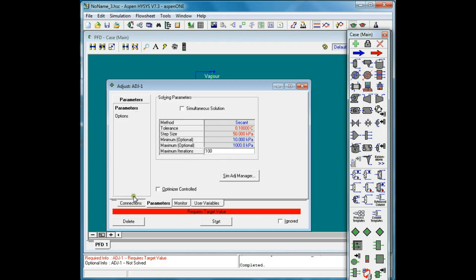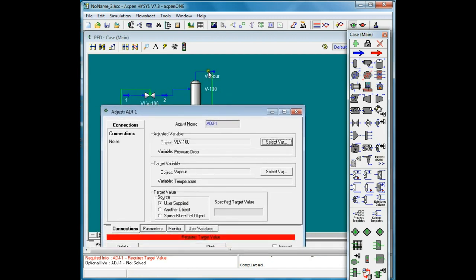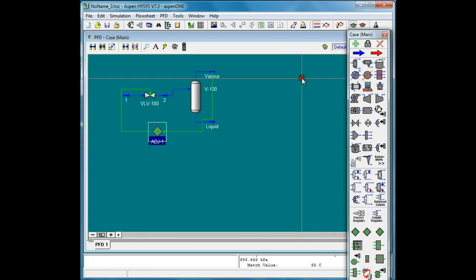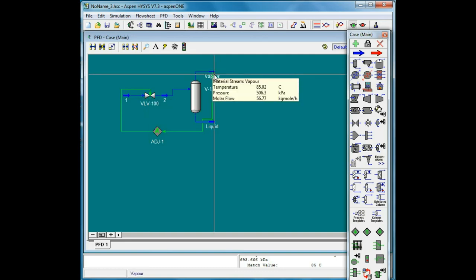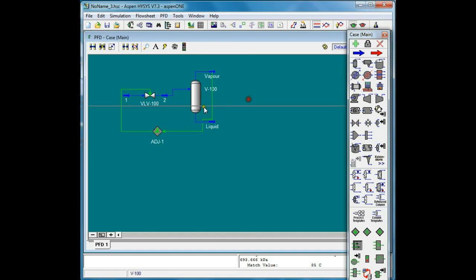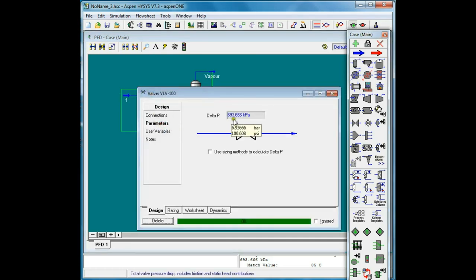Now let's go back to the connections tab where I specify the temperature I'm looking for. I'll set this target temperature to 85. When you start, you can see that the Adjust Block has set the delta P so that we get 85 degrees centigrade at the outlet. The temperature is 85.02 and the delta P is 693.6.